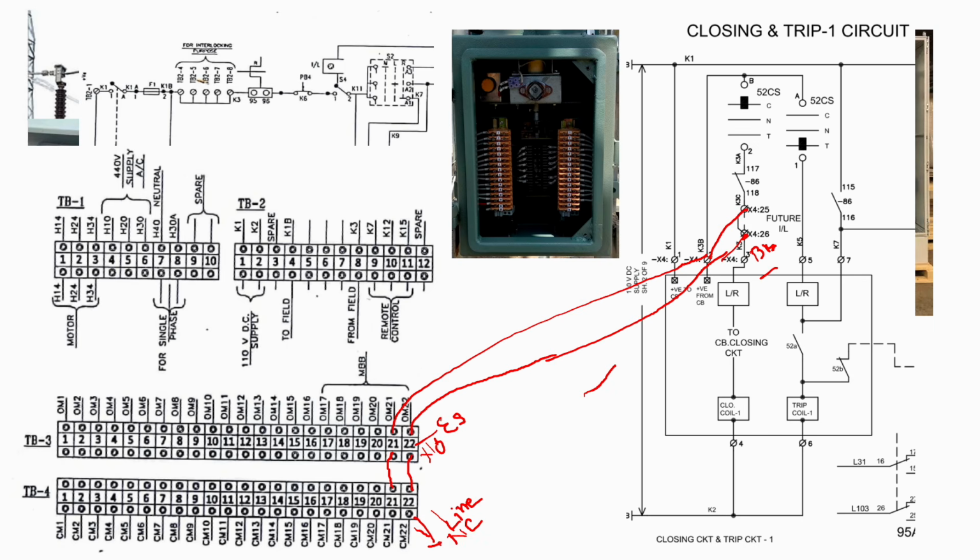So this is a perfect interlock with earthing switch, which is very important for safety reasons, because whenever my earthing switch is closed, my breaker will not get closed and the isolator at that time will remain open. So you will get a dual interlock here.